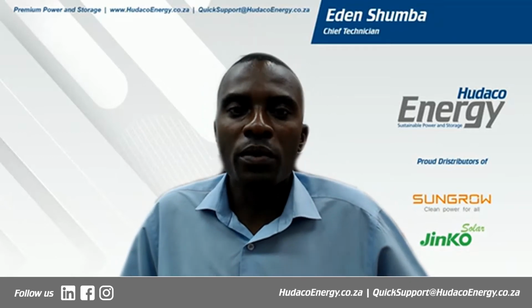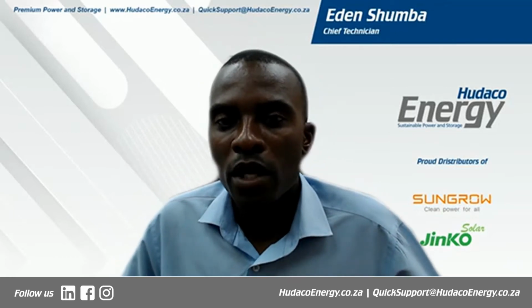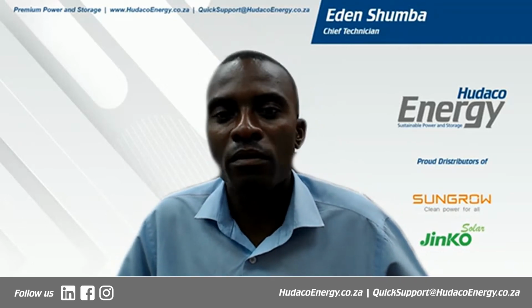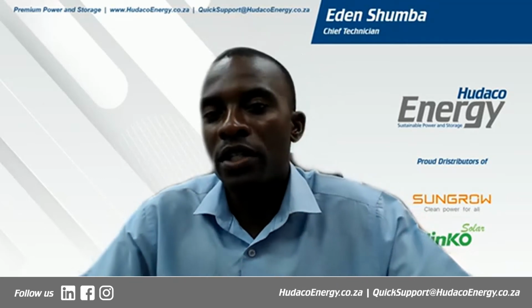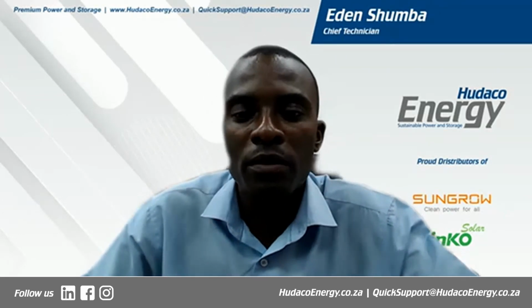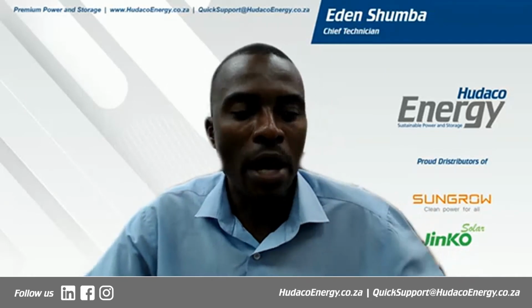All right. So when we say they are high voltage batteries, we mean they are not your standard 48 volt batteries, because most of the time, most installers were used to brands like Pylontech and Shoto, which are 48 volts. These ones, the minimum we start at is 168 volts, going up.